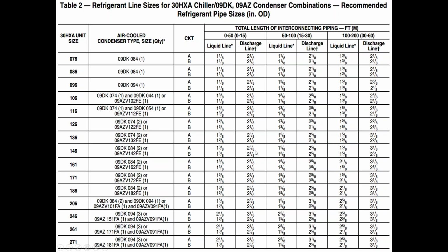What's a minimum load valve? Well, think a hot gas bypass with a new name. That's what it is. So if you have the minimum load on these chillers and the condenser is above, and like a suction line, if the vertical section is longer than 3 feet, we need to do a double discharge riser. So always look at our little notes, our little asterisks, our crosses, there's X's, we have all kinds of stuff in there, or just simply numbers like 1 through 10. Always see what the note says, and always note that in this case on the HXAs.